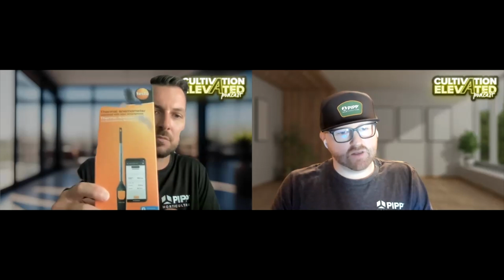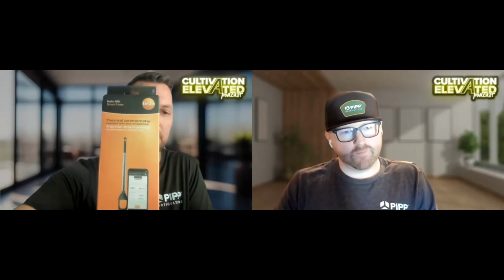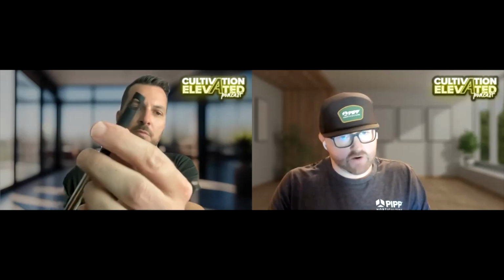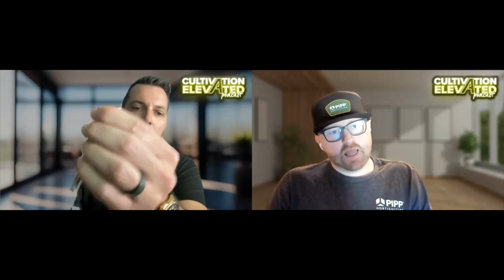Instead, there's a much more sensitive tool called a hot wire anemometer. It looks like a little stick. Oh yeah, you've got one right there, with the box. A hot wire works a little differently, but it is a better tool for the air velocities we're targeting in indoor cultivation. There's a little wire that is heated up by a voltage, and that little bead right there is a very small probe. That's what's called a unidirectional anemometer. If you look on the tip of that too, there's an arrow, which denotes the direction of airflow.